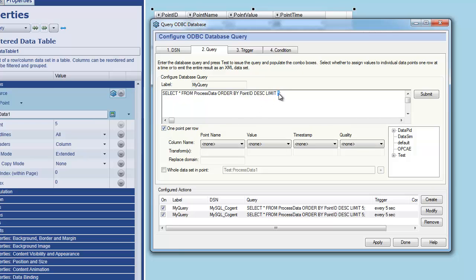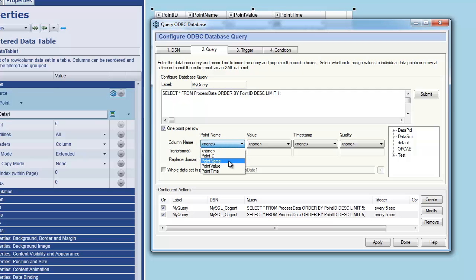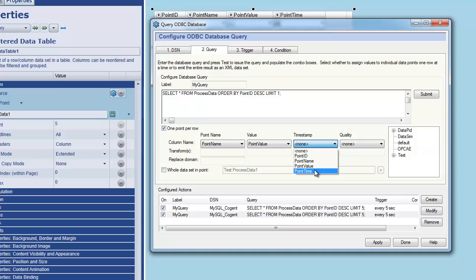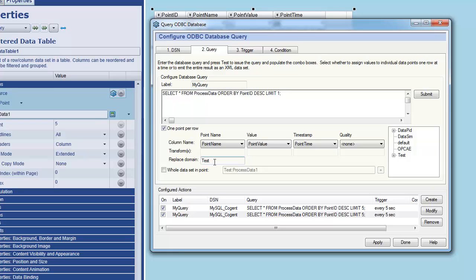And rather than five rows, let's change this to one. I just want a single row to be returned. And I want to create a new point and the point name is going to be the point name that I read back from the SQL table. The point value is obviously going to be the point value. Timestamp is going to be timestamp. We don't have a quality but that doesn't matter. And this point, the new point that I'm creating, I want it to be stored also in my test domain.